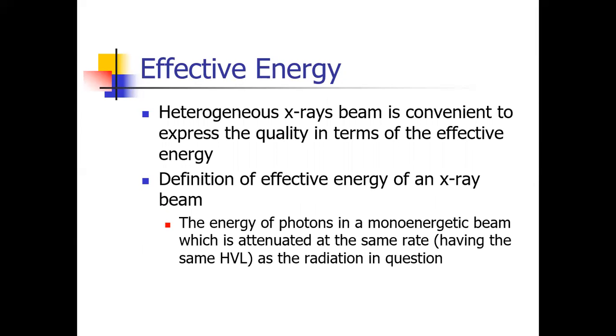Now, the effective energy. Heterogeneous X-ray beams are convenient to express the quality in terms of the effective energy. The definition of effective energy of an X-ray beam is the energy of photons in a monoenergetic beam, which is attenuated at the same rate or having the same half-value layer as the radiation in question.